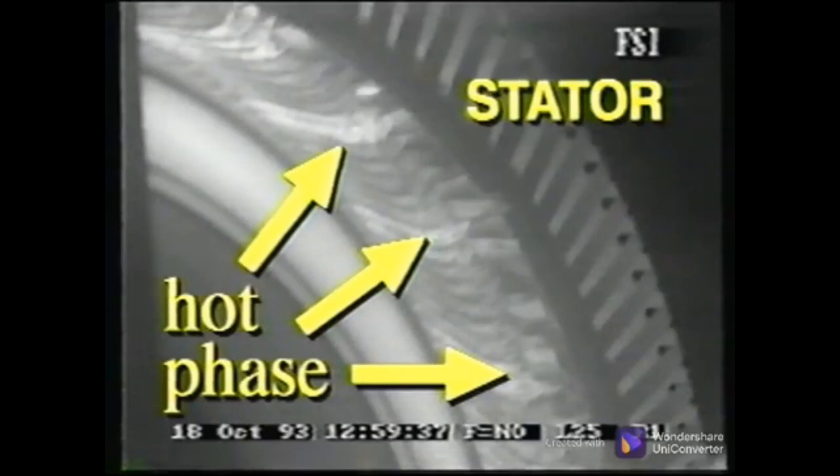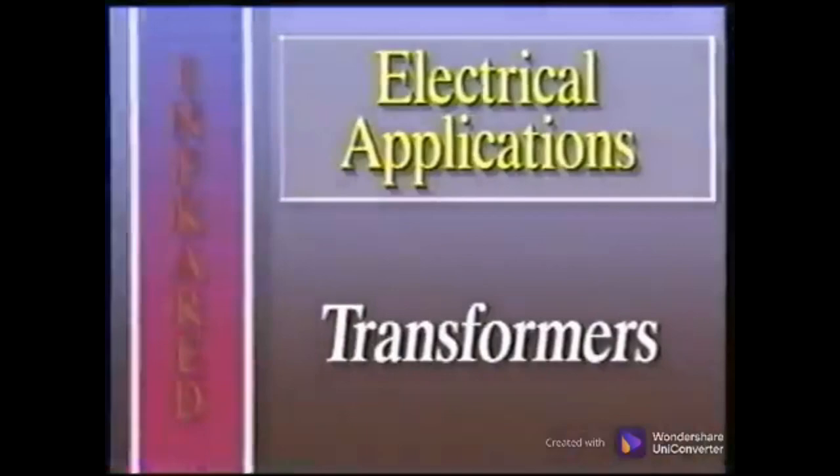A problem in the stator of a motor can cause one leg or phase to draw more or less current. In most applications, the phases should all have approximately the same load and therefore the same temperatures. One leg that is hot indicates uneven phases, and other tests should be performed to determine the actual source of the problem.